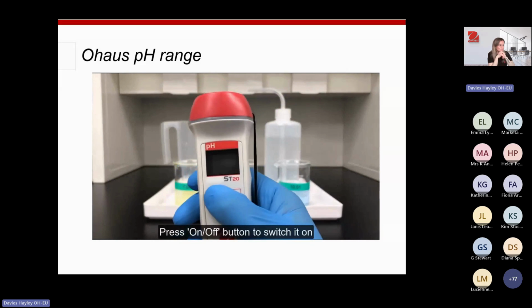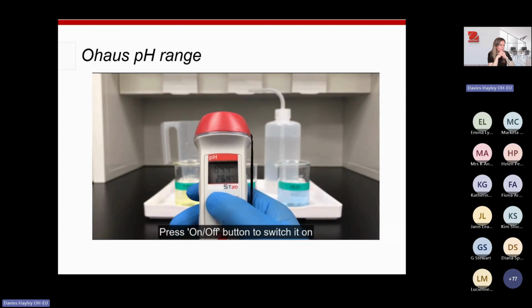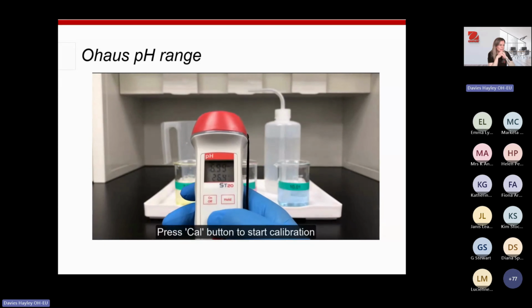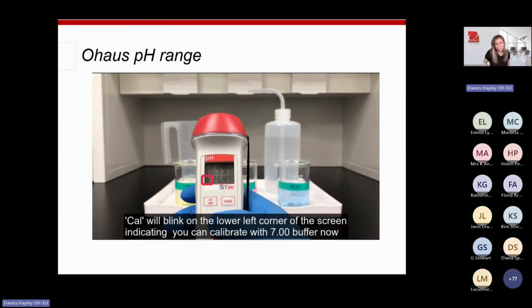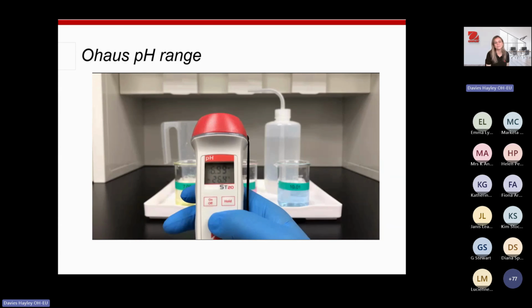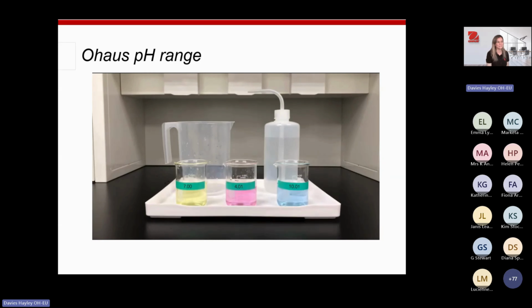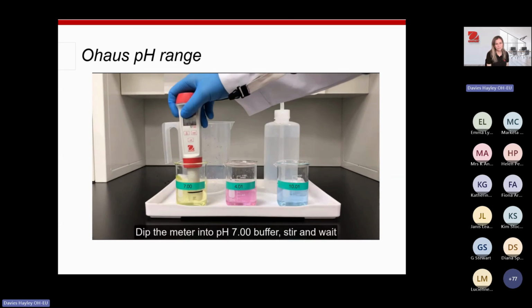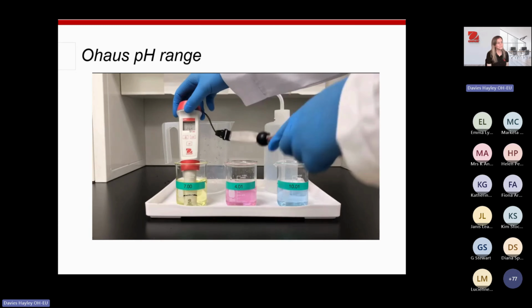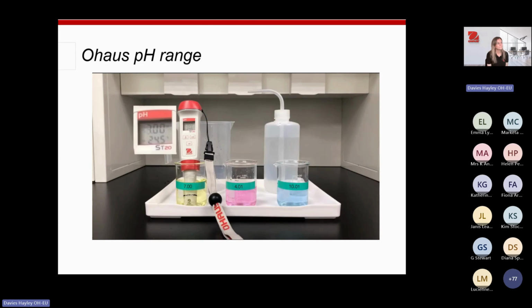On the meter, you will switch it on, and you will press the cal button, and it will blink, and it will know what pH buffers you need, and it will automatically start. It will start with the pH 7. So you'll notice it's given a gentle stir, and you just leave that in the beaker and that will calibrate. Doesn't take too long.